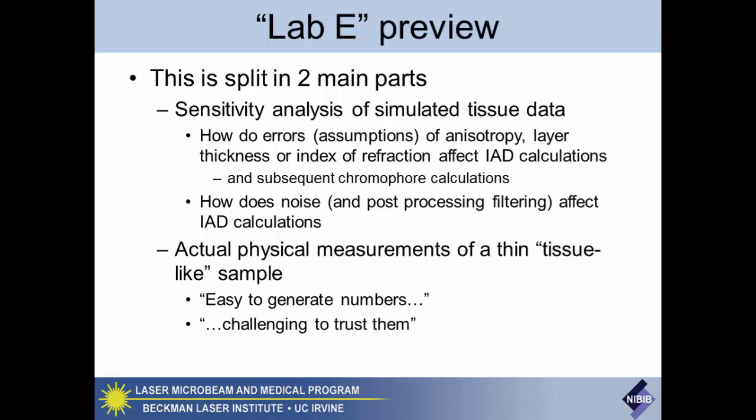Making a measurement of that gives the total amount, the 100% amount of light you can possibly get. And then for our zero, we close the shutter to the lamp, so that when you make your measurement, it's only the dark noise of your spectrometer and any stray light that might be in the system, to characterize that.